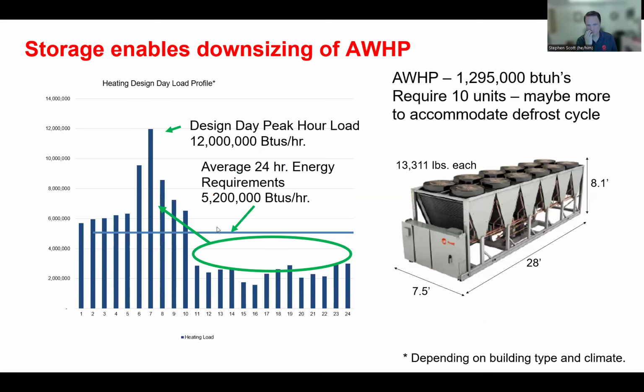Yes, this one. Okay, so the 7 a.m. heating load, what this shows is that, say today, without storage, if you have to size for your heating load, you size an air-to-water or air source heat pump based on the peak instantaneous heating load you need for that day, plus an amount for defrost, because on a design day it's going to be minus something, much more below zero outside.